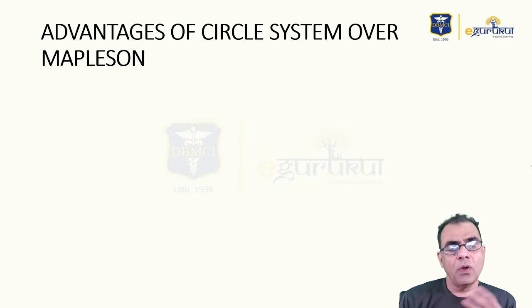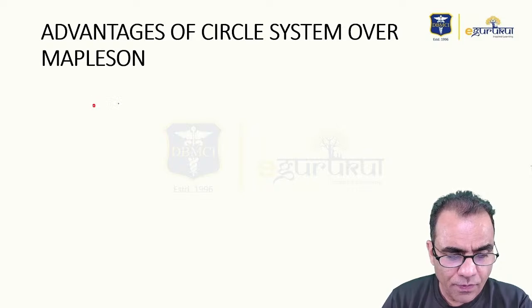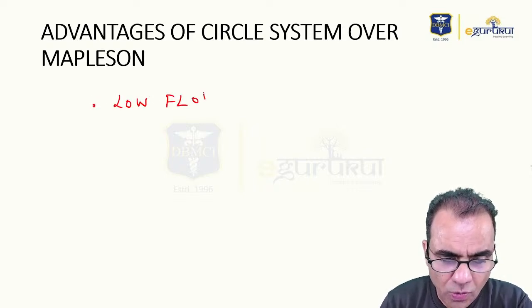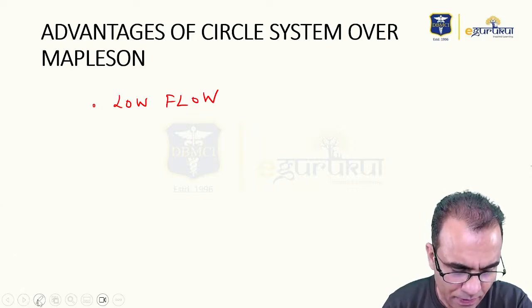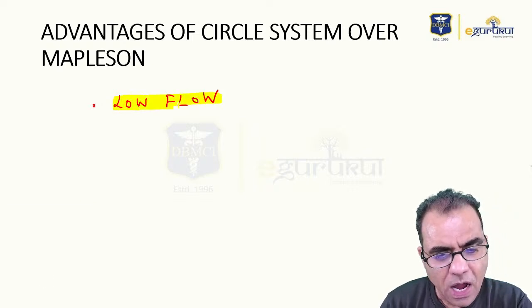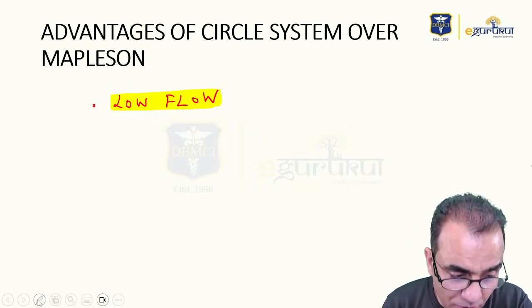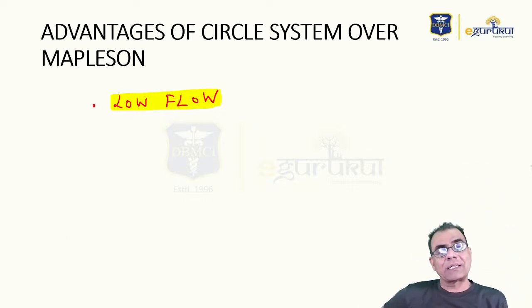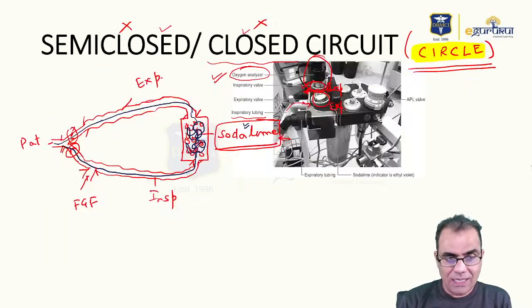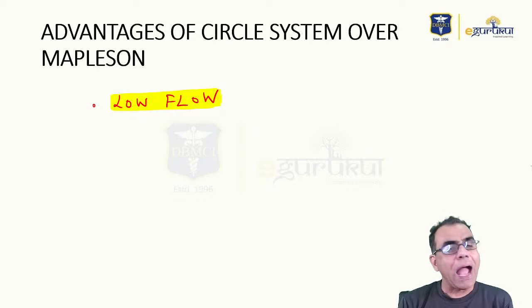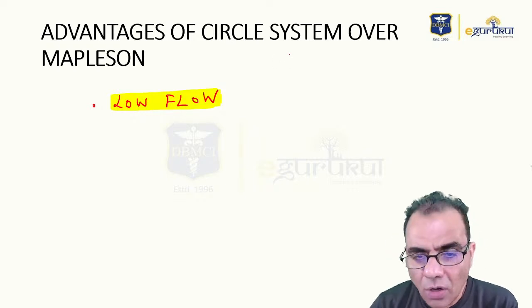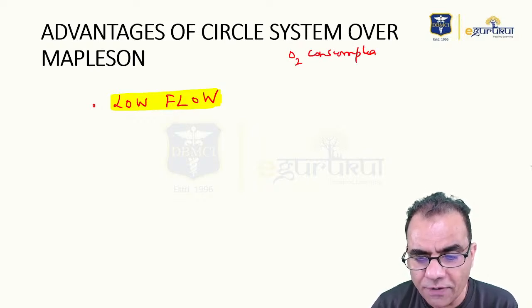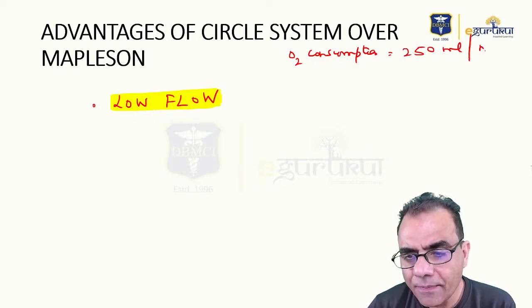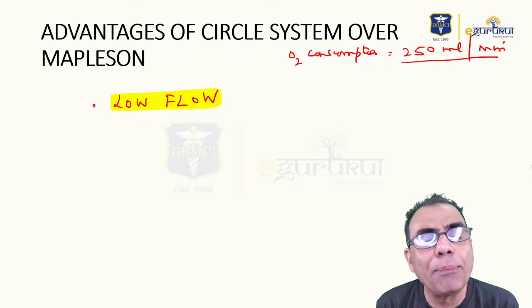Now, comparison. What are the advantages of the circle system over Mapleson? The biggest advantage, I will say, is low flow. How much flow is needed in the circle system? Same gases are being reused, so only the oxygen consumed by the body needs to be replaced. And how much is the oxygen consumption per minute? You must have read in physiology, 250 ml per minute. Means this 250 ml of oxygen needs to be replaced.